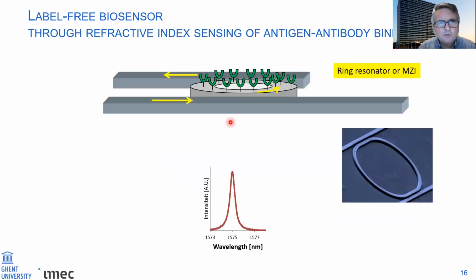Okay, let me start with probably the most common type of device based on integrated photonics in the medical field. That's the biosensor. It's also called a label-free biosensor. It's a refractive index sensing device based on antigen-antibody binding. What really happens is that you have this device. This is a so-called ring resonator. Here you see an electron microscopy picture of such a ring resonator. You have an input waveguide here. Light comes in here, but then passes very close to this ring waveguide, close enough so that part of the light will couple to the ring. Light will circulate in the ring. It's a resonator. Part of the light will couple out from here, and the rest of the light will couple out from here. This is a resonant device.